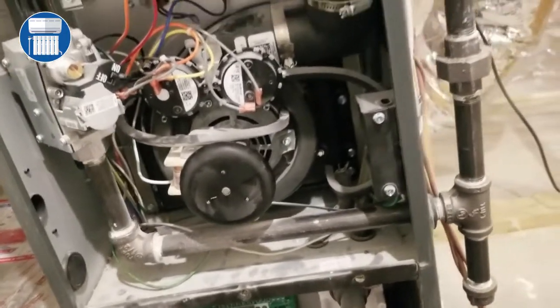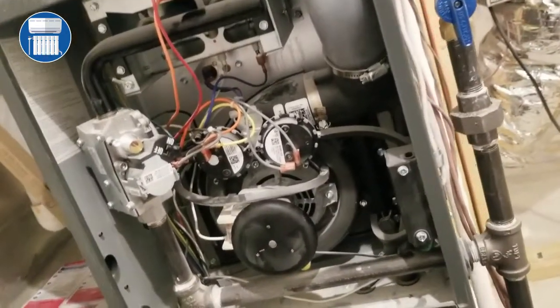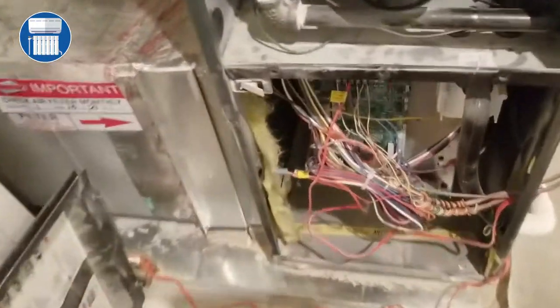That could save you thousands of dollars. Let me look here to see if there's a damper here so I could show you. It's kind of hard to see in this unit, but going up there, there's a damper up there. I don't know if you could see it. There's a handle for a damper right there. If that is closed, you will actually go off on high limit. So you may want to open that if somebody closed it by mistake or something like that. You may want to check on that.